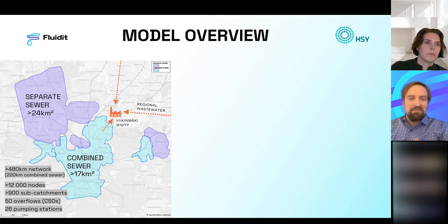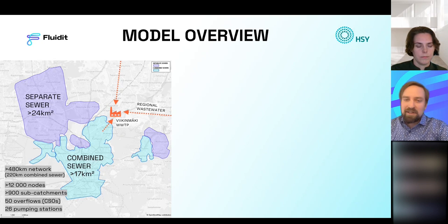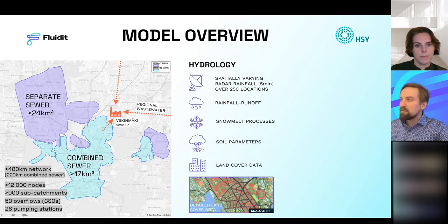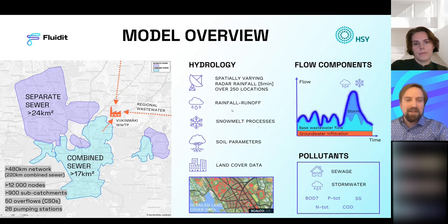Currently there is roughly 17 square kilometers of combined sewer system, with quite large separate sewer areas that connect through the combined sewer area, as well as regional flows taken into the Viikinmäki treatment plant calculations. From the hydrologic point of view, it's a very interesting model. We are using radar rainfall — this is the first time I think it has been used at this scale; it hasn't gone without problems, but at least we get better representation of spatial variability. We are modeling all rainfall runoff processes on the catchments, including snowmelt, with soil parameters estimated and many things derived from land cover data.